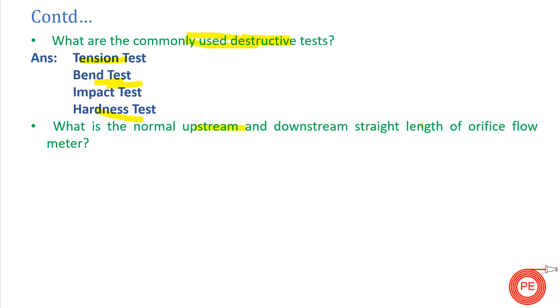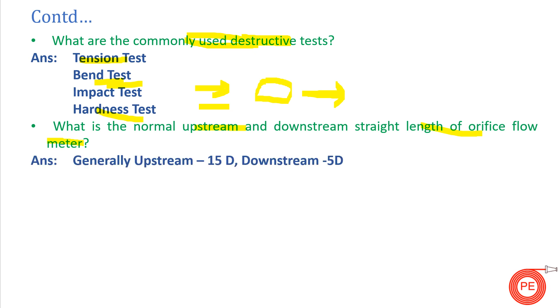What is the normal upstream and downstream straight length for an orifice flow meter? Upstream is the direction from which flow is entering, and downstream is where it exits. To provide an accurate reading, there must be sufficient straight pipe distance because bends or walls can cause flow fluctuations, giving incorrect readings. The upstream length is kept at 15D and the downstream length at 5D, where D is the pipe diameter.